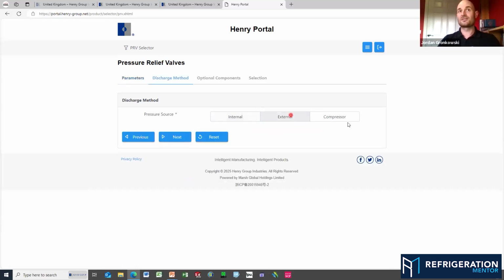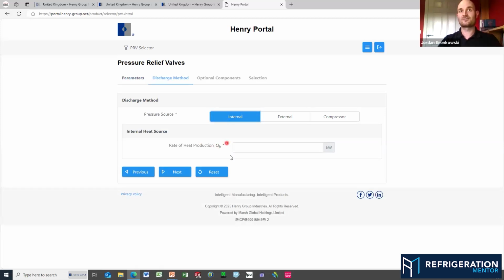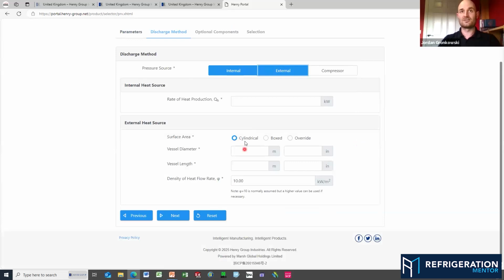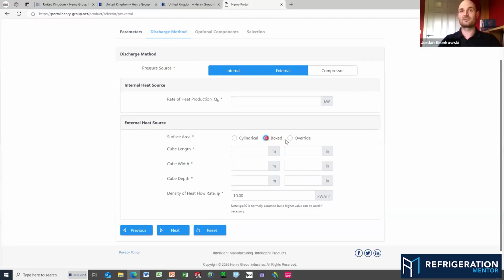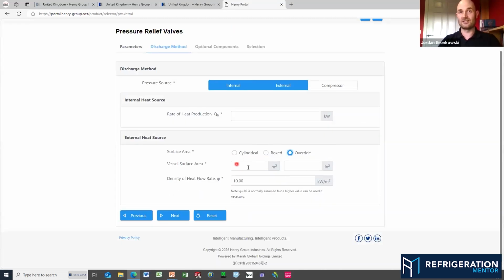Next, this is our 3 discharge methods. So this is what we talked about. We've got internal. There's your QH term, asking you for that. You can click external as well. And again, this is your cylindrical. Is it a box? Do you know the surface area? You can just override it by putting in the area. And again, you can use meters or inches, doesn't matter. Here's your density of heat flow rate term we talked about. Normally, this is what the standard said, 10 is normally assumed, but a higher value can be used if necessary.